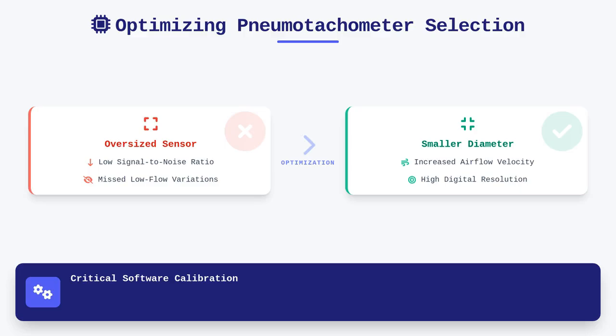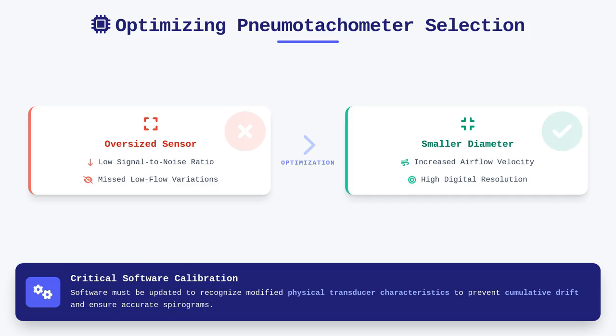This hardware change forces a necessary revision of our circuit software configurations. We must ensure the software is calibrated to interpret these faster pressure changes and recognize the modified physical characteristics of the smaller transducer. Otherwise, the integration of flow to volume will result in cumulative drift and inaccurate spirograms.